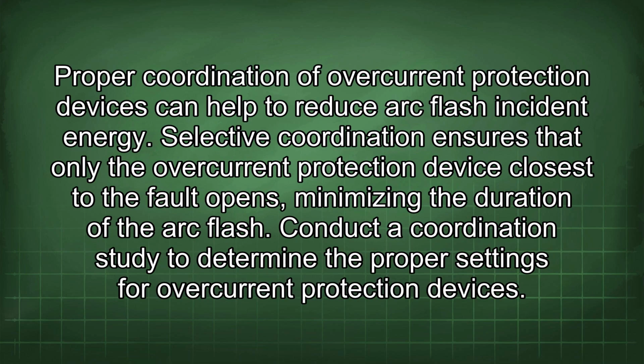Proper coordination of overcurrent protection devices can help to reduce arc flash incident energy. Selective coordination ensures that only the overcurrent protection device closest to the fault opens, minimizing the duration of the arc flash. Conduct a coordination study to determine the proper settings for overcurrent protection devices.